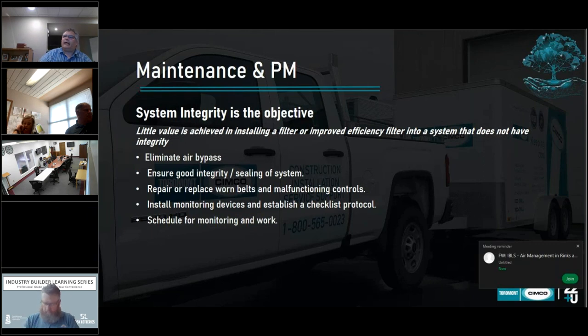So you've really got to take the data. You've got to start eliminating air bypass, seal your system up, make sure belts are being replaced on a regular basis, repair your malfunctioning controls, and look at monitoring devices. Have you got a checklist protocol? Do you schedule? Do you monitor? How do you work, how do you do your maintenance?